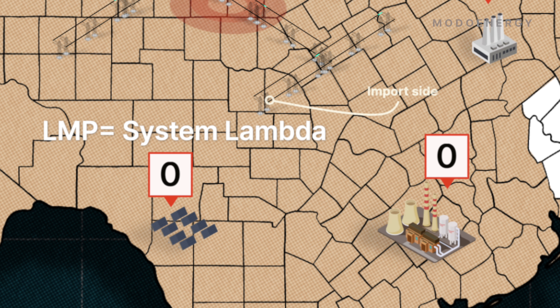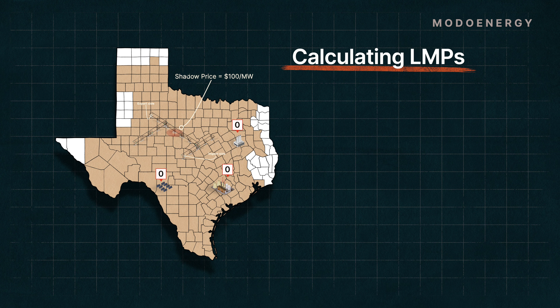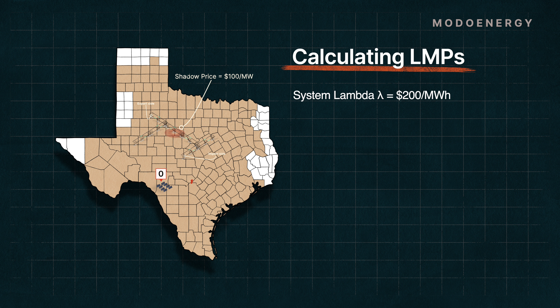For the vast majority of resources across ERCOT, this tends to be the case for a given constraint. To illustrate actually calculating LMPs, let's start by saying that the system lambda is $200 per MWh. This means that those resources with 0% shift factors will also have LMPs of $200 per MWh.